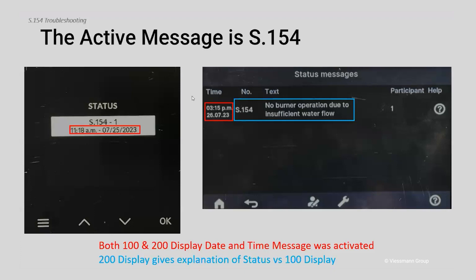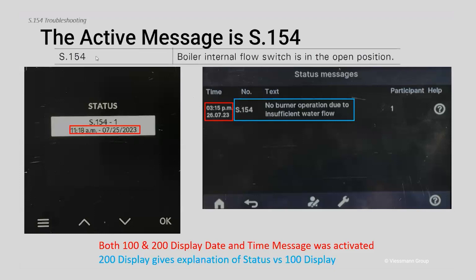The 100 boiler will give you the status message but not a definition — you get the date and time and would have to go to the manual. There it is: S154, and the reason why the status message is occurring is because the flow switch is in the open position when the boiler wants to fire up for a temperature set point. If you have the Viessmann fault code checker — available as an app on our website — you can key in the message. Make sure to use the little period: S.154. It's a fault code checker, though, so it would only relate to fault codes (F.whatever).